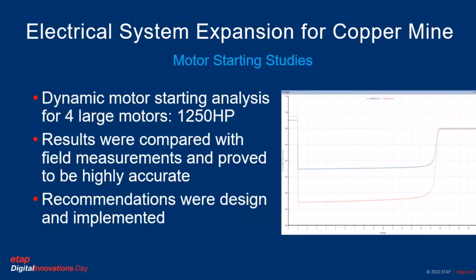Since we involved very large motor startups, up to 1,250 horsepower, the voltage drop that occurs during the half cycle is very important to see if the motor will reach synchronism or not. That is especially needed in the case of a weak power system. The results of the motor start were compared with the field measurements and proved to be highly accurate. We made some recommendations to the client, which in many cases have been implemented.